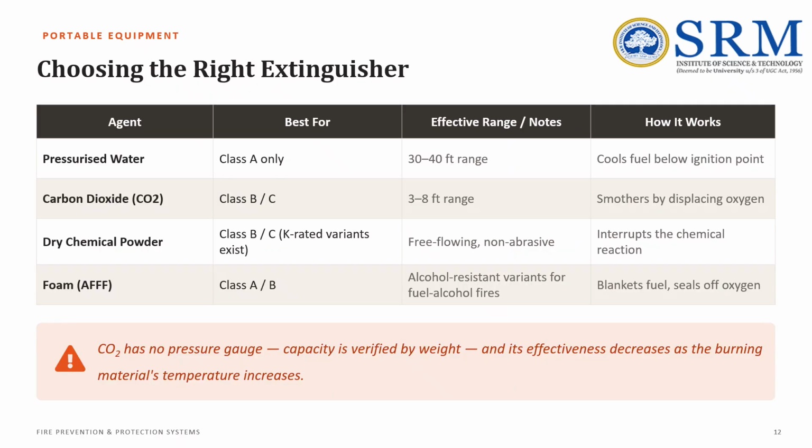So different extinguishers are suitable for different fire classes. Water extinguishers are used only for class A fires because they cool the burning material.